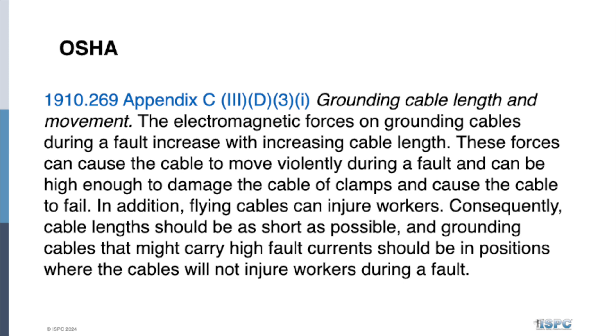So the other thing we've talked about a little bit is length of cable, right? The longer the cable, the longer the resistance. Well, the other thing that happens when it comes to length of conductor when we're talking about our grounding that we install for our protection is not only does that length of cable increase the resistance in our grounding configuration, but it can also cause mechanical damage, right? And I'm going to show you some examples here in a little bit of where grounds are applied for the protection of personnel, right? And to get the system to trip off as quickly as possible should there be a fault.